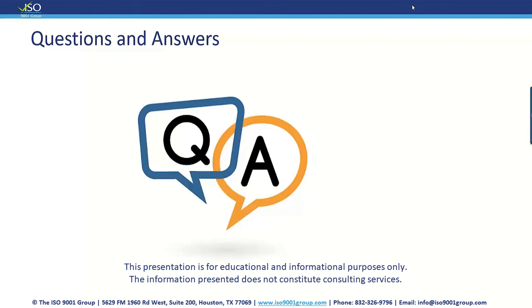So maybe that's what the person means when they say an impact analysis, and the impact could be pretty significant. But this is another thing that I've seen companies do. Maybe the device is out of calibration only by date, meaning that it was due to be calibrated by October the 27th, 2020, and you're using it today, and by date, it appears to be out of calibration. But it's reading properly. If you verify it is reading properly, that means it's actually in calibration. But that's where you put yourself in that little box, because you set yourself up with an annual calibration versus verifying if the equipment is reading properly and then sending it out for calibration. So I think a lot of people are having these impacts based upon the date, and the equipment is actually reading properly.